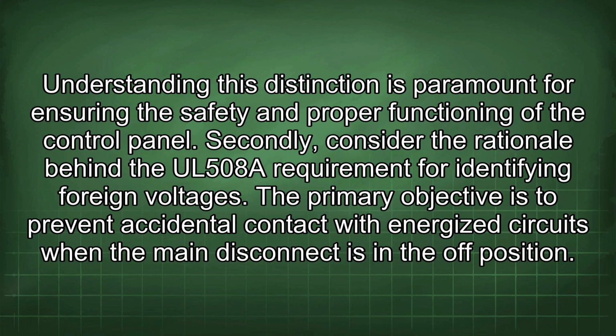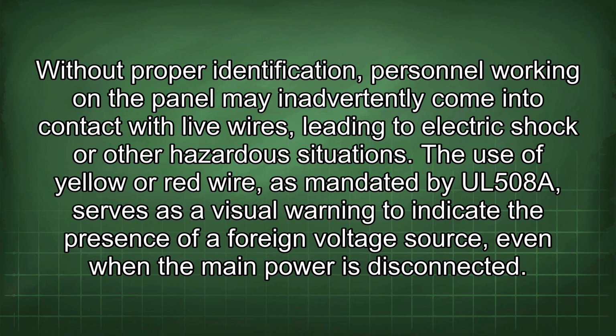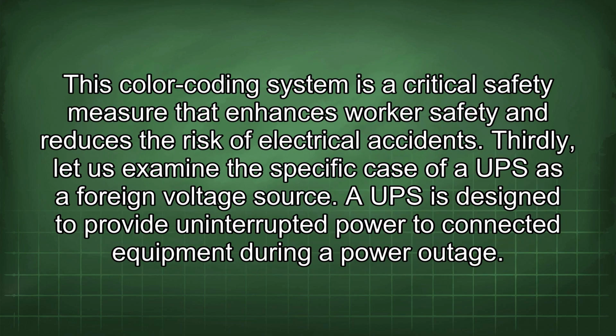Secondly, consider the rationale behind the UL508A requirement for identifying foreign voltages. The primary objective is to prevent accidental contact with energized circuits when the main disconnect is in the off position. Without proper identification, personnel working on the panel may inadvertently come into contact with live wires, leading to electric shock or other hazardous situations. The use of yellow or red wire, mandated by UL508A, serves as a visual warning to indicate the presence of a foreign voltage source, even when the main power is disconnected. This color coding system is a critical safety measure that enhances worker safety and reduces the risk of electrical accidents.